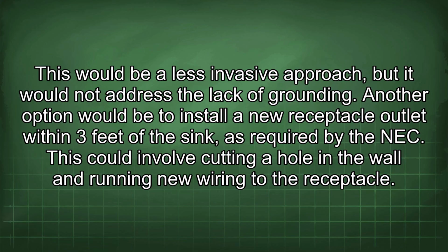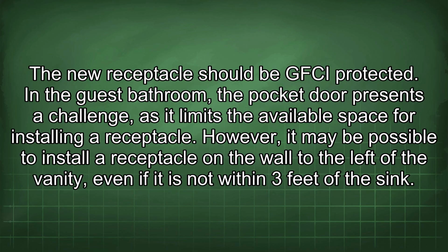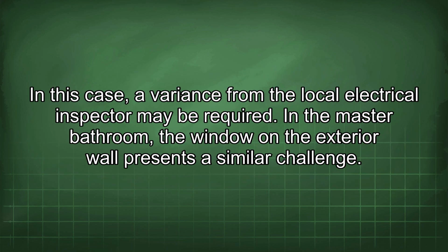Another option would be to install a new receptacle outlet within 3 feet of the sink, as required by the NEC. This could involve cutting a hole in the wall and running new wiring to the receptacle. The new receptacle should be GFCI protected. In the guest bathroom, the pocket door presents a challenge, as it limits the available space for installing a receptacle. However, it may be possible to install a receptacle on the wall to the left of the vanity, even if it is not within 3 feet of the sink. In this case, a variance from the local electrical inspector may be required.